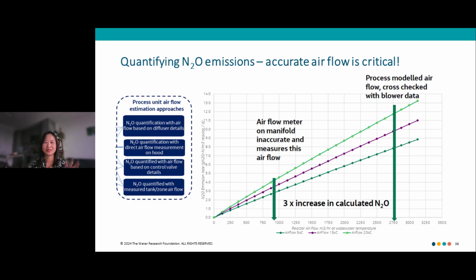And really just to bring this up again, most of the time, the concentration measurement can be pretty accurate as long as you're measuring within the detection range of the sensor you choose. This is an example where we have an airflow meter that's 3 times wrong. So as you can see, the uncertainty here is way higher than the analyzer inaccuracies.